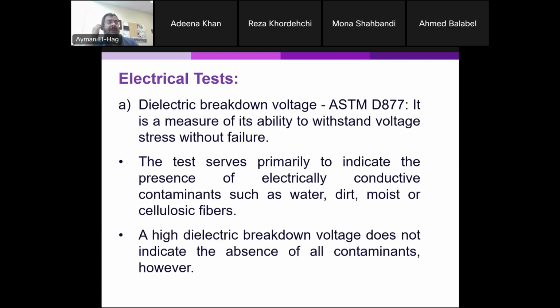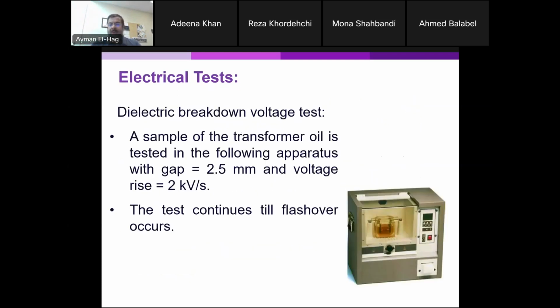So in my opinion, this is one of the least sensitive tests that reflects the quality of the oil, but nevertheless, most of the utilities have this test because it's an easy test, and it gives them some indication about the strength, because once the oil cannot withstand the voltage, it becomes really bad, and you have to take action immediately if it reaches that level. So how is the test done? Basically it is an automated test. So nowadays you don't need to do it manually.